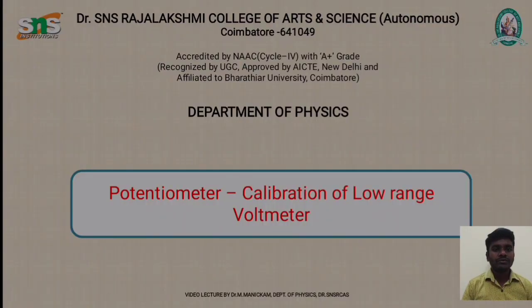In this video we discuss the potentiometer calibration of a low range voltmeter. We have taken a voltmeter of range 0 to 6 volts to calibrate. Calibration means measuring the voltage point by point, inch by inch, with the help of the potentiometer using the low range voltmeter. If it functions properly as per the voltage provided by the potentiometer, then the voltmeter is calibrated. This is the procedure we are going to follow.